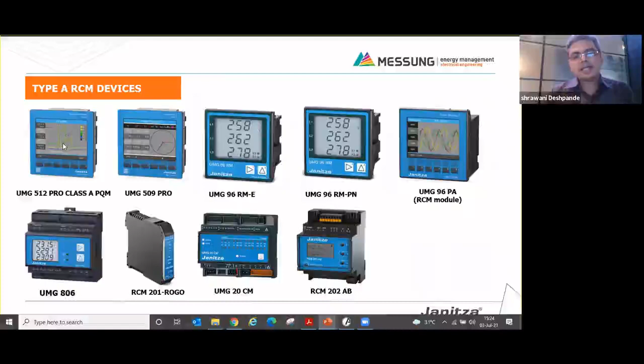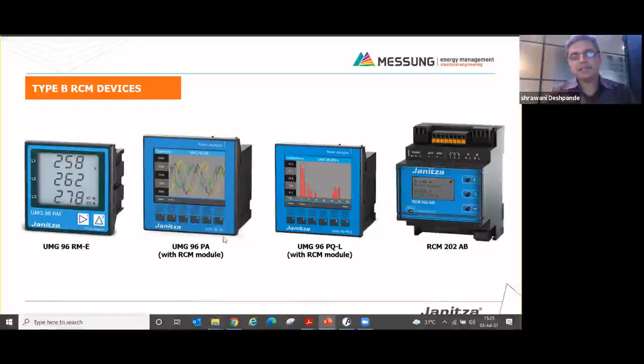These are the type A RCM devices where we can identify type A problems, that is 50 Hertz frequency. In type B, that is 2 kilohertz problems, we can identify with these Janitza devices: UMG 96 RME, UMG 96 PA, UMG 96 PQL, and RCM 202 AB. For type B plus, the UMG RCM 202 AB is an exclusive RCM device. Here we can identify all three types of RCM problems, that is A, B, and B+.